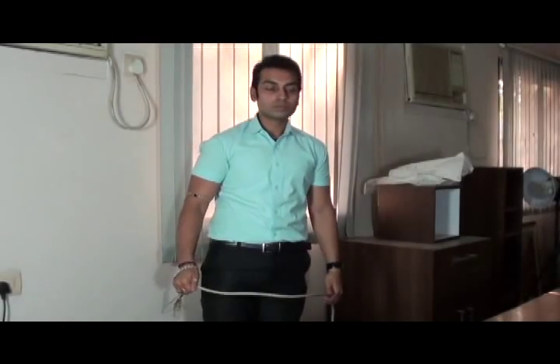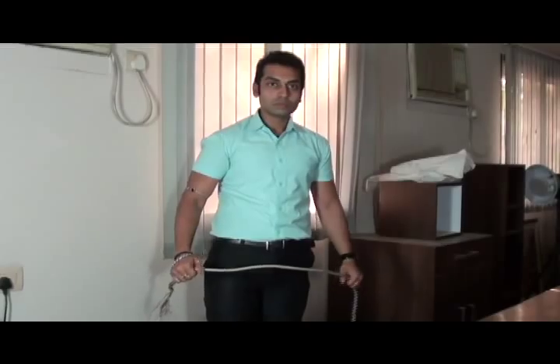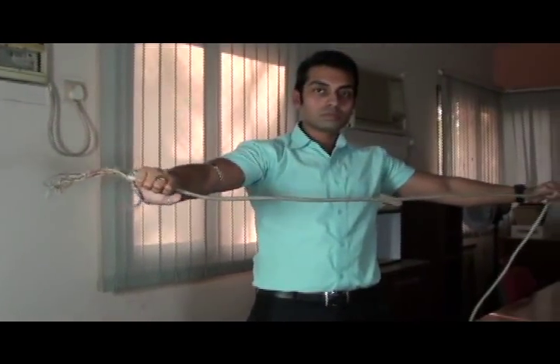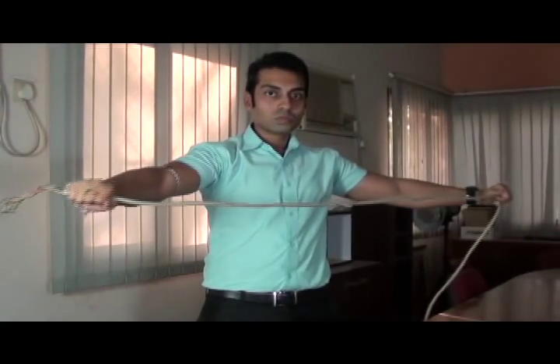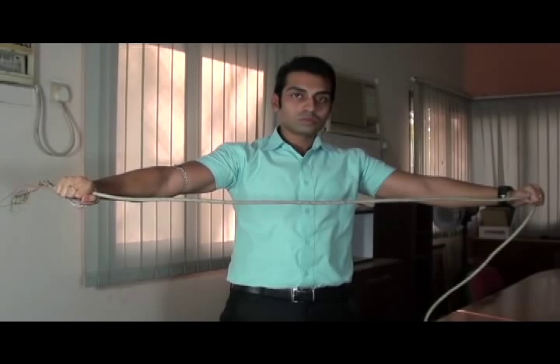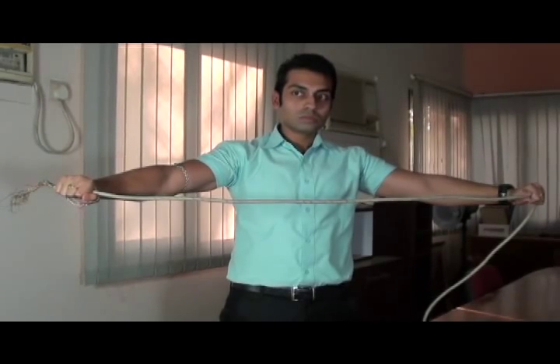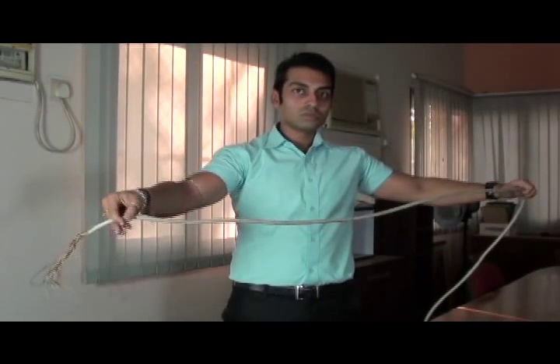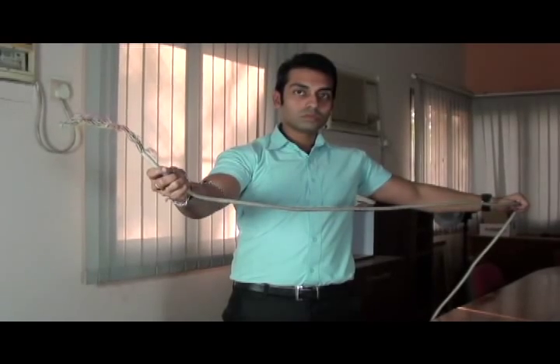Before the instrument is put into use, we take a sample of the type of cable to be tested for faults whose length is known for fixing the velocity propagation of the sample cable. We have measured this cable and the length of it is 6.47 meters.